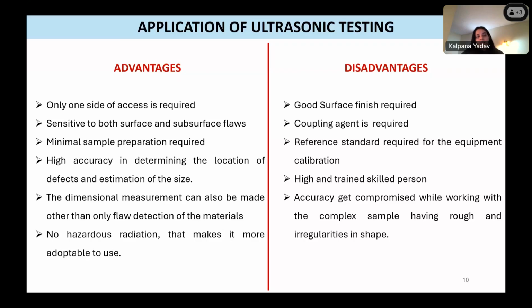This technique is sensitive to both surface and subsurface flaws, and minimal sample preparation is required. You don't need to prepare the samples before testing them. They should just be clean, with no liquid couplant or mix of couplants on them. There is also higher accuracy in determining the location of defects and estimating their size. Dimensional measurement can also be made, other than flaw detection.